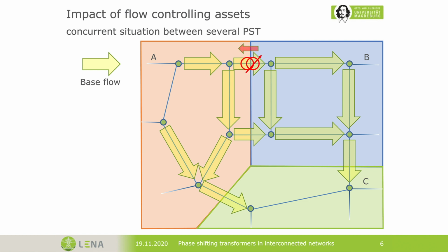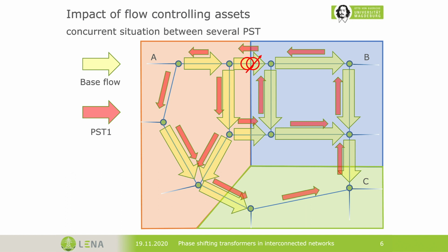Now you can see zone A is exporting, and let's say the interconnector on top is the weakest one. So this is the one that gets congested first. And we want to remedy this congestion using a PST. So we will definitely place a PST here because it's the most effective position. And I showed you already that this PST will cause flows on all the other lines. So this is what the result may look like. And you can see that our line where the PST is positioned can be very nicely remedied. The congestion is gone, but you can see all of the other interconnectors are utilized a little bit more by the circular flow.